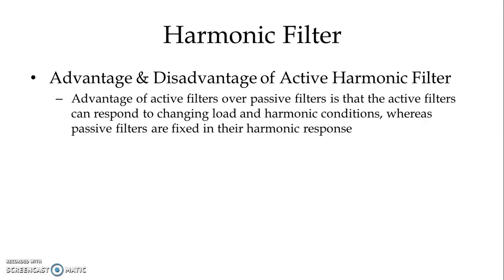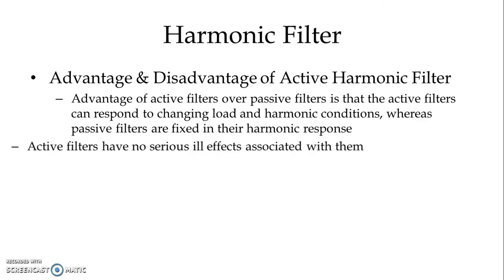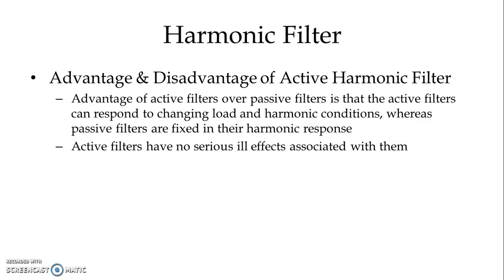The advantages of active filters over passive filters are that active filters can respond to changing load and harmonic conditions, whereas passive filters are fixed in their harmonic response. Active filters have no serious ill effects associated with them. In the case of passive filters, we have to take care during design to avoid parallel resonance with the source impedance. At the same time, active filters are very expensive and are not advisable for smaller power systems.